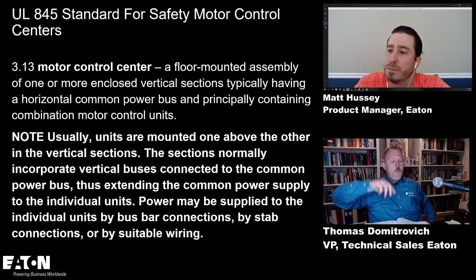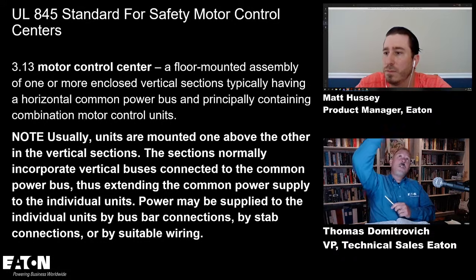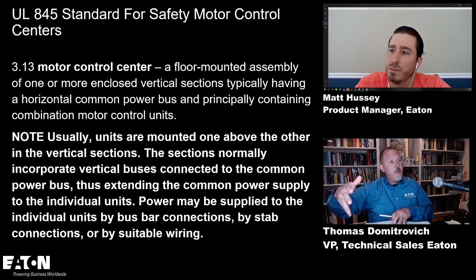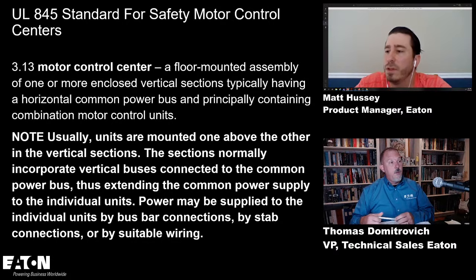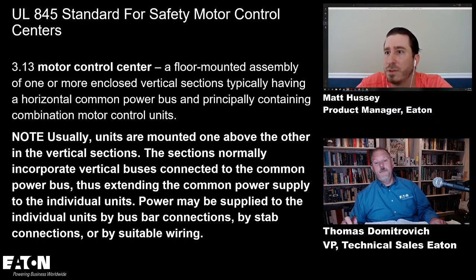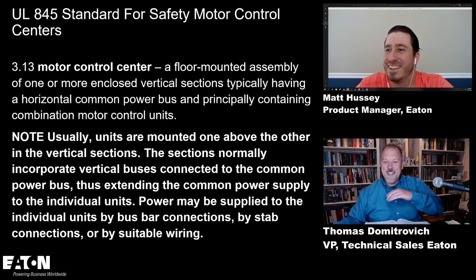So overall height, if I'm standing in front of an MCC, what's the top of that MCC? Is there a maximum that the standards tell you, or is it just driven by how far away the handle needs to be from the floor? Yeah, you're thinking of the top of the disconnect. I think the 2 meter rule. But yeah, MCCs are going to be 90 inches tall across manufacturers. They can be shorter. What's the shortest one you've ever made? We've actually made one that was under 6 feet tall. It was kind of cool whenever we were seeing it go through the shop. You had somebody leaning on it with their elbow on top. That's pretty cool. Yep.